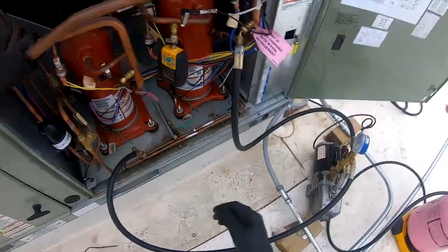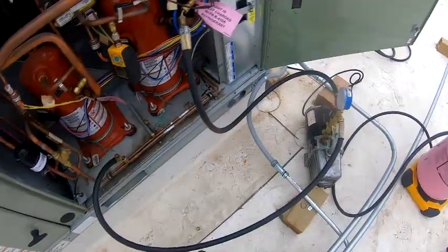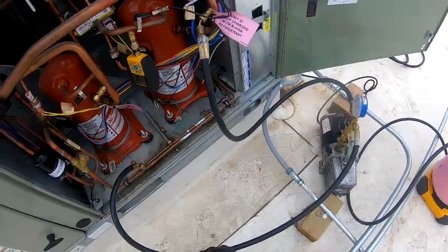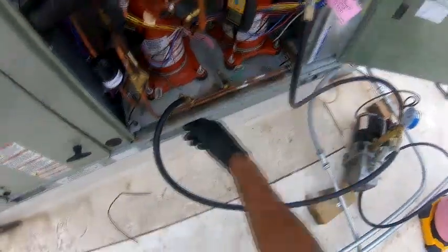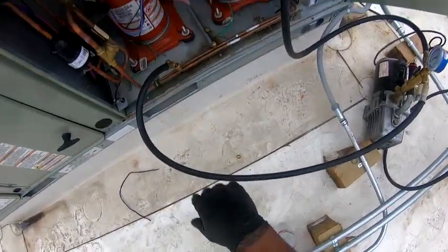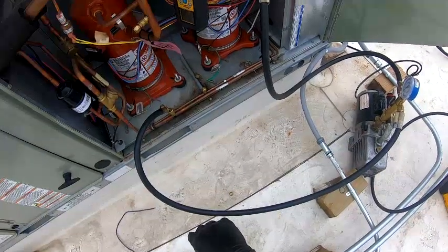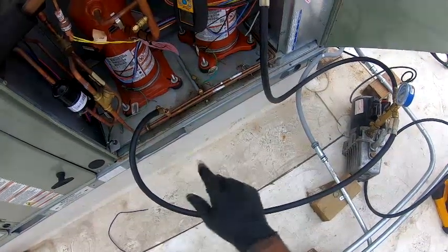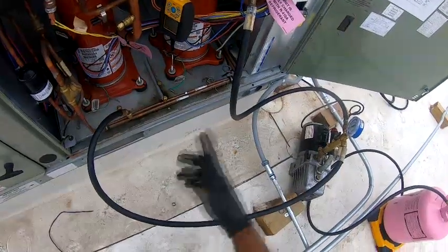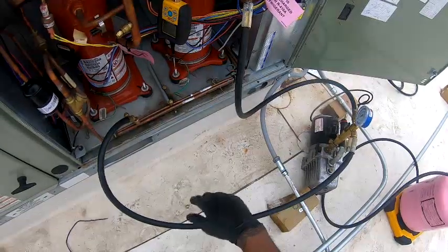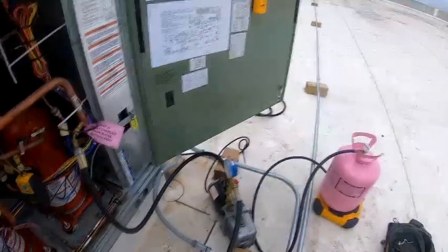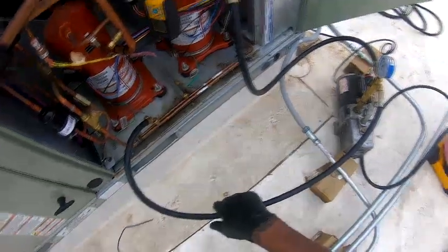Normally I have my Schrader core removal tool, where I can valve off the lines when I add my refrigerant. But since I didn't use the core remover tool, I can't isolate the lines. So I'm going to lose some refrigerant in the hose. But the valve stems are still in there, so it won't be too bad.